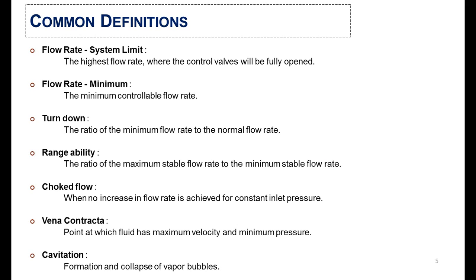There are some common definitions required before moving to the sizing of the control valve. The first one is the flow rate: the highest flow rate where the control valve will be fully opened is called the system limit flow rate. The second is the minimum flow rate that can be controllable by the valve. The third definition is about turn down: the ratio of the minimum flow rate to the normal flow rate is called turn down.